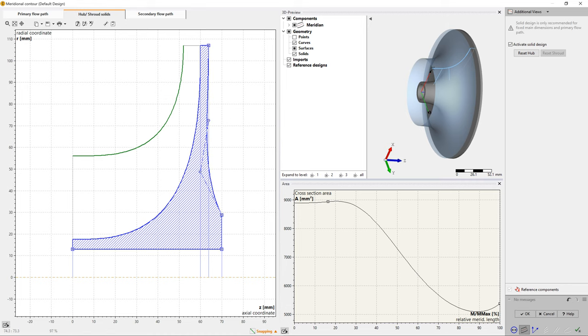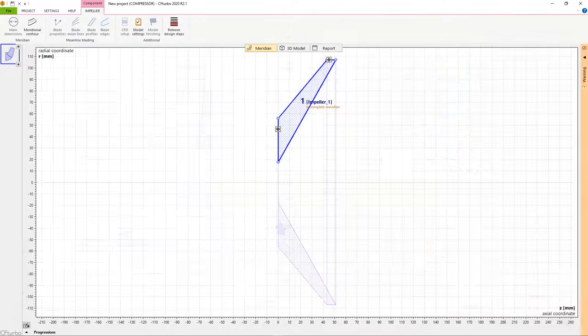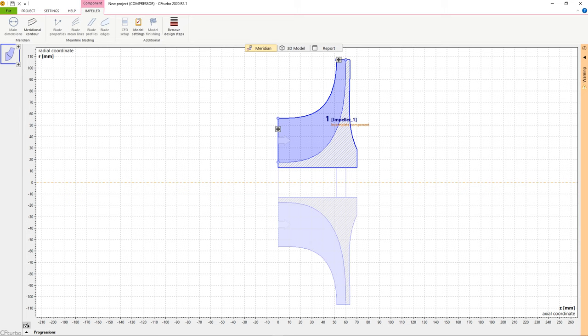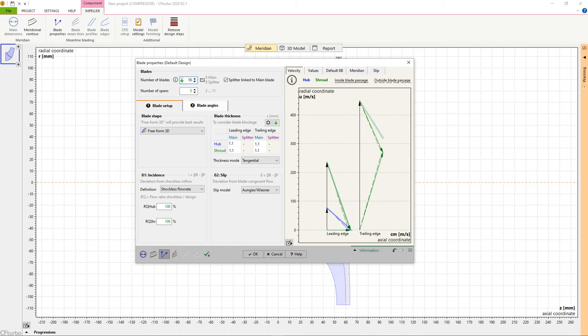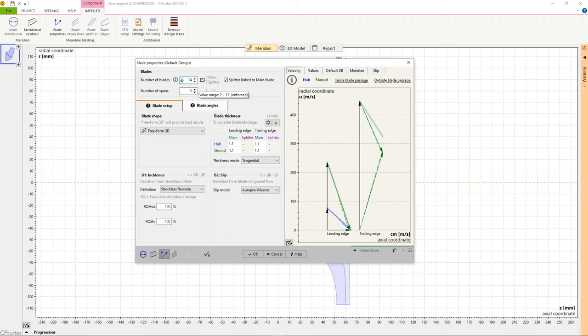The next impeller design step is about blade properties. It mainly comprises the calculation of blade angles at leading and trailing edges of main blades and splitter blades. Several options for slip factor correlations are supporting this design step.